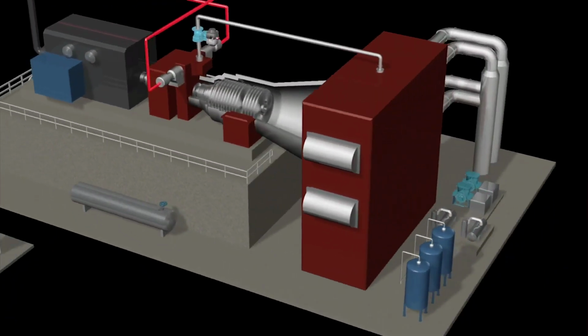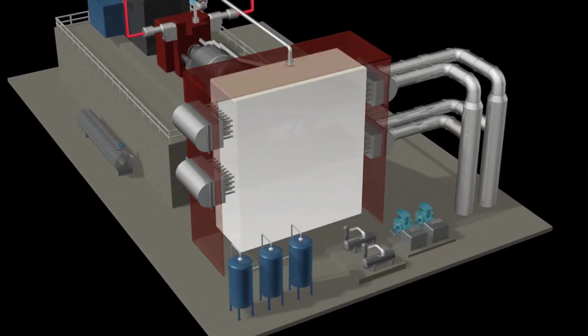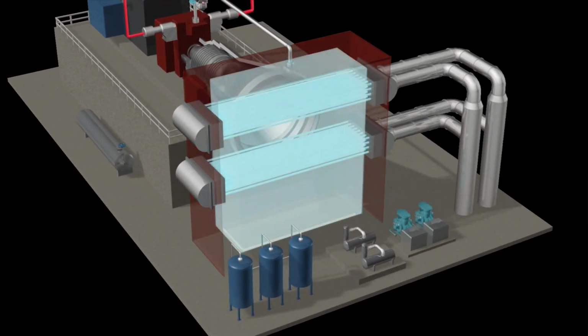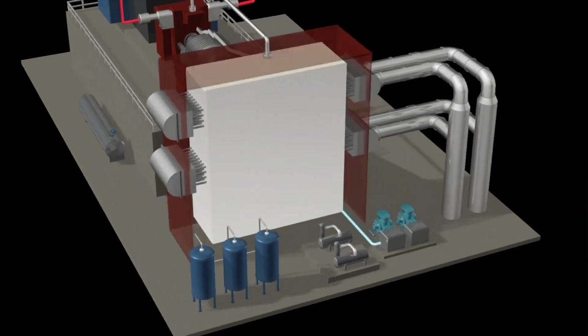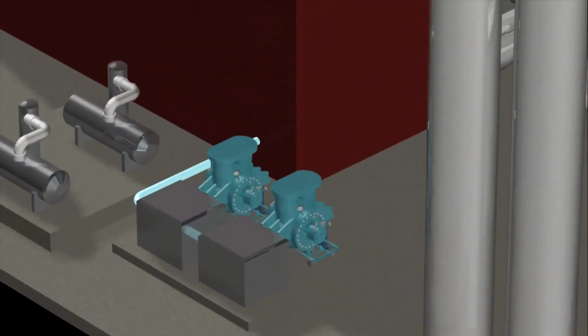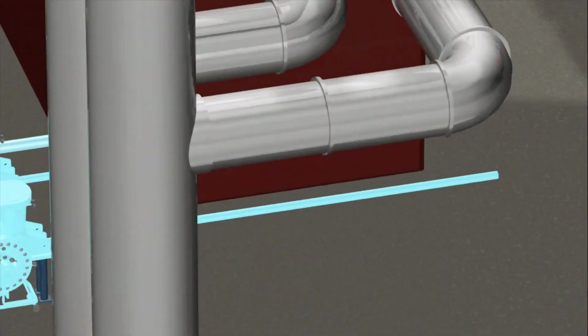Additionally, a NuScale SMR-based power plant has black start capability, allowing it to start up from cold conditions without external grid connections. A single NuScale power module, NPM, can supply all the house load electricity needs of the plant while also continuing to provide power to a local industrial customer or mission-critical facility without external grid connection via a microgrid connection.